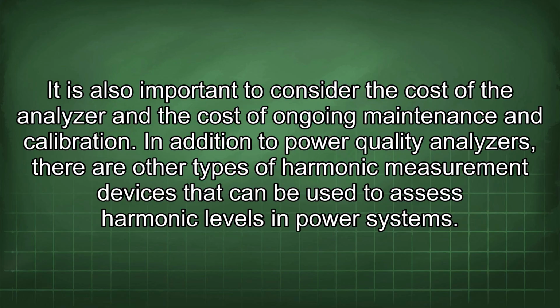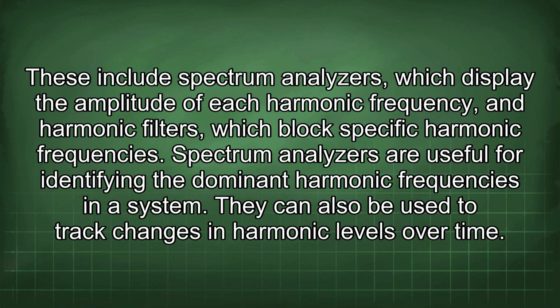In addition to power quality analyzers, there are other types of harmonic measurement devices that can be used to assess harmonic levels in power systems. These include spectrum analyzers, which display the amplitude of each harmonic frequency, and harmonic filters, which block specific harmonic frequencies. Spectrum analyzers are useful for identifying the dominant harmonic frequencies in a system. They can also be used to track changes in harmonic levels over time.